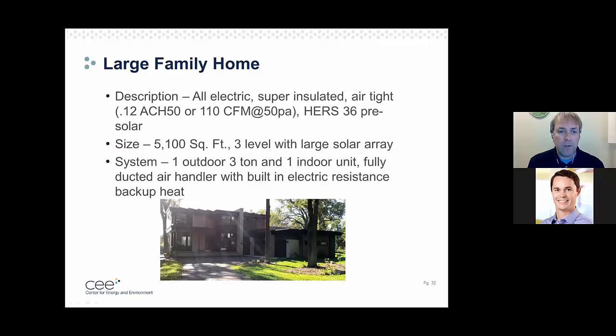It's very large though, 5,000 square feet, 3 levels, and then there'll be a big solar array up on top of the roof. The system here is 1 outdoor 3-ton and then 1 indoor unit, a fully ducted air handler with a built-in electric resistance backup heat. So it's rated for about 38,000 BTU of heat at 5 degrees. So it's a very small system, or heat amount needed, for this huge house. Normally you'd probably see a 60 to 80,000 BTU furnace in a house this size that's built to code standards. So definitely got that load really down, so you could put this nice heat pump in.